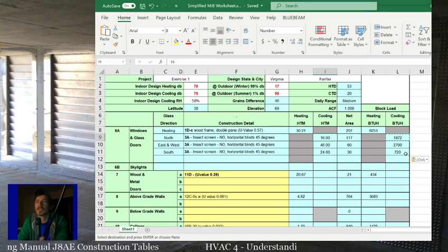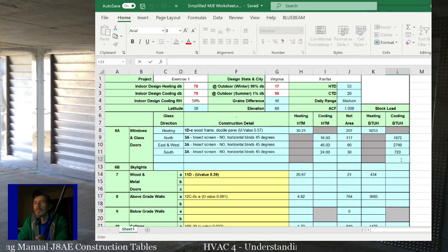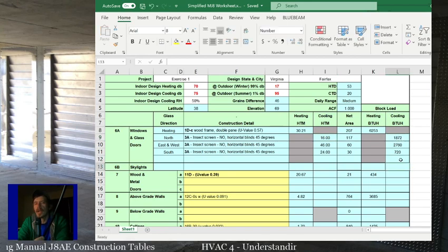And it's very important to take that into account, but again, most of the houses that are built don't have significant shading over the windows unless there's like a deck or something over it, right? And that's the most common situation where you have a shaded window. So you just need to remember that if you have a deck or something that goes over top of the windows so the windows never get any sun, just put those in your table as if it was a northern window. Even if it's on the south side of the house, put those shaded windows in with your north windows and you'll be doing it right.